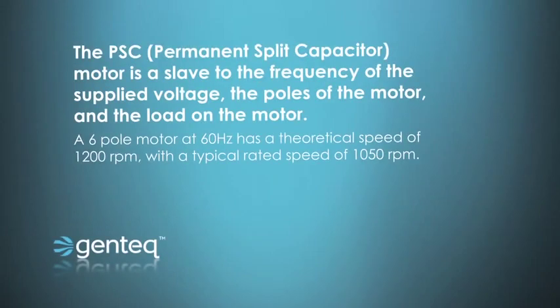The limitations of a PSC motor are simply the fact that it's built with a limited amount of poles and it's operated by a specific frequency. Most of your indoor blower motors, PSC, are six pole, which means they are going to run around 1200 RPMs because of the 60 cycle frequency that is delivered to the motor. The motor is limited by the gearing or the amount of poles that are in it, which cannot be changed, and it's limited by the frequency delivered to the motor — kind of like having an engine in your car that only runs at one RPM. There's no way to change that.